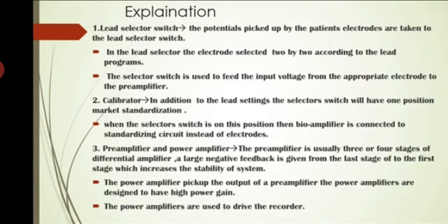Second, calibrator. In addition to the lead settings, the selector switch has one position marked as standardization. When the selector switch is in this position, the bioamplifier is connected to a standardizing circuit instead of the electrodes. So using this calibrator, they are standardizing or checking the working of the amplifier as well as the electrodes, meaning whether it is working properly or not. They are making the calibration of the circuit or electrodes.